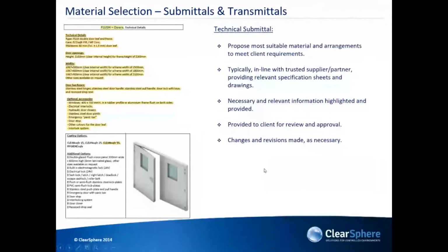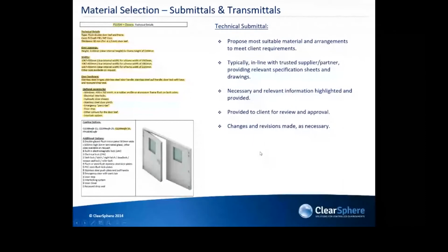Just to give you an idea, on the technical submittals we propose the most suitable materials and arrange to meet client requirements, typically in line with trusted suppliers and partners. We've partnered with Kingspan for many years on the cleanroom system. They provide the doors, walls, vision panels, so it's all from one supplier, and they have an extensive testing regime for fogging and hydrogen peroxide testing of materials, with documentation to back it up. We work well together and have a lot of background information relevant to the client when setting out their cleaning regimes on site.